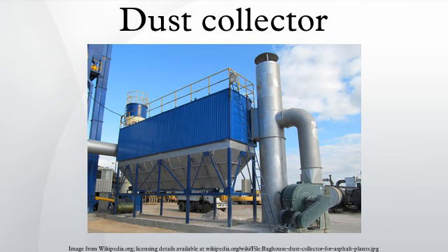Types of bag cleaning. Baghouses are characterized by their cleaning method. Shaking. A rod connecting to the bag is powered by a motor. This provides motion to remove caked-on particles. The speed and motion of the shaking depends on the design of the bag and composition of the particulate matter. Generally, shaking is horizontal. The top of the bag is closed and the bottom is open. When shaken, the dust collected on the inside of the bag is freed. During the cleaning process, no dirty gas flows through a bag while the bag is being cleaned. This redirection of airflow illustrates why baghouses must be compartmentalized.